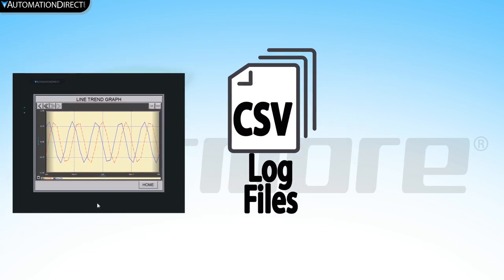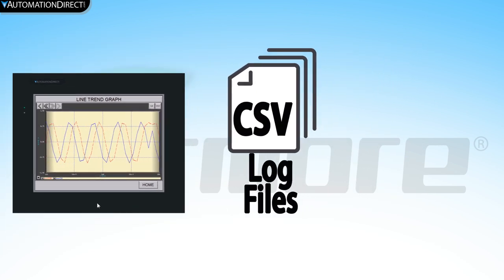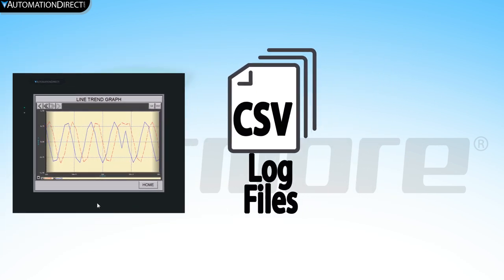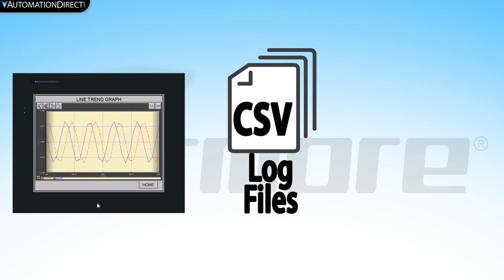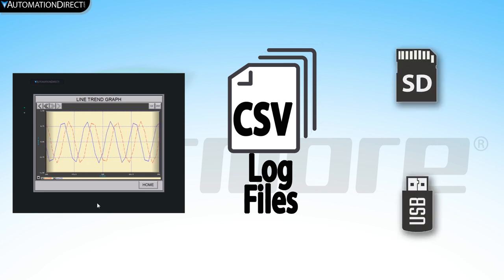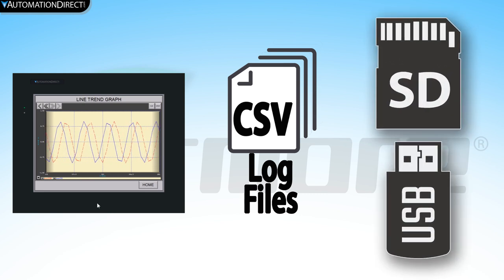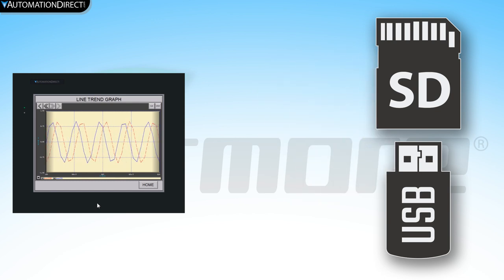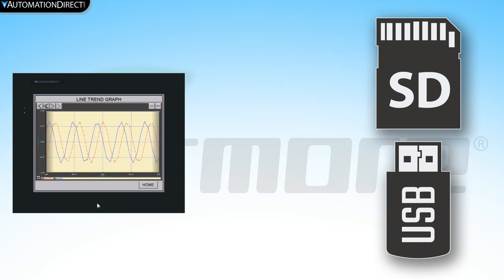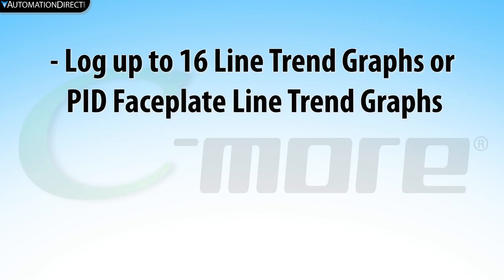This file logs for 24 hours and a new file is created each day at midnight. The file can then be stored on an external USB or SD drive. You can simultaneously log data from 16 line trend graphs or PID faceplate line trend graphs.